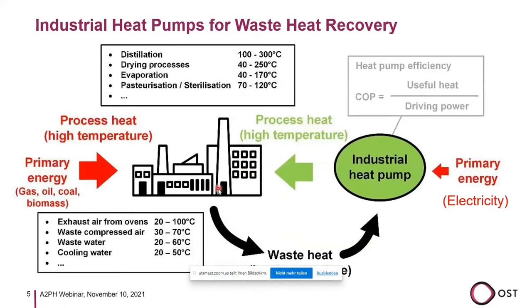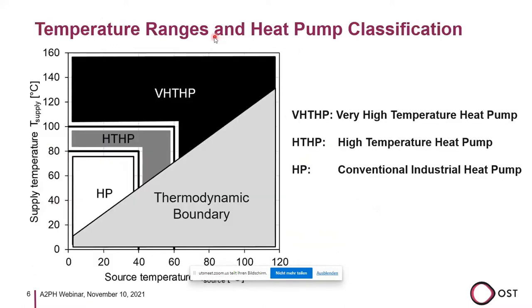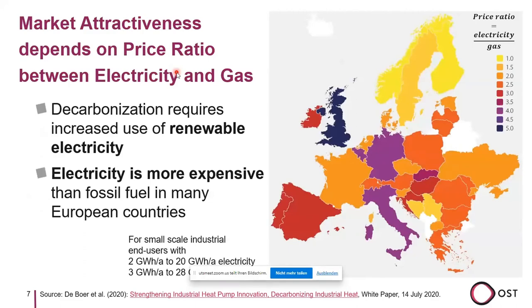In the industry, we normally have a primary energy consumption: gas, oil, coal, and biomass. It produces processes and then has waste heat, and this waste heat is useful heat for the heat pump, which is driven by electricity, and it generates higher temperature heat again. So it is closing the energy cycle. When we look at the temperature ranges, we can structure the heat pumps by the supply temperature and the source temperature. Here we are like in conventional industrial heat pumps up to 80 degrees, up to 100 degrees supply temperature. We can speak about high temperature heat pumps and higher, very high temperature heat pumps.